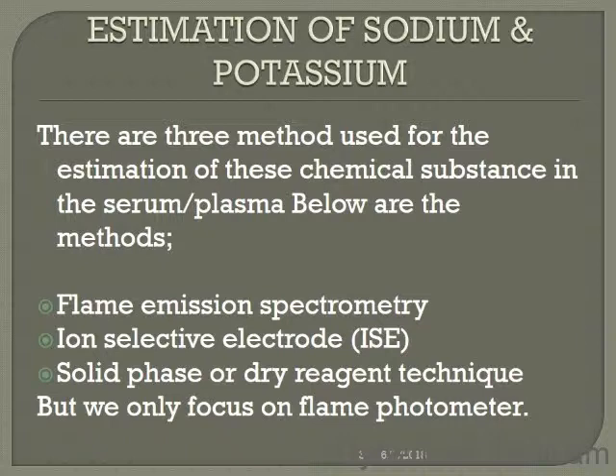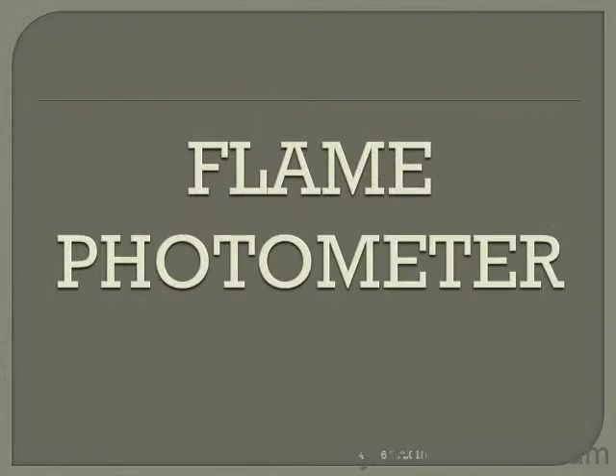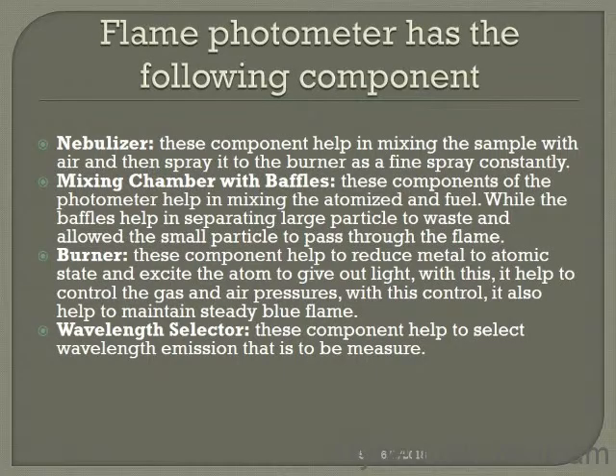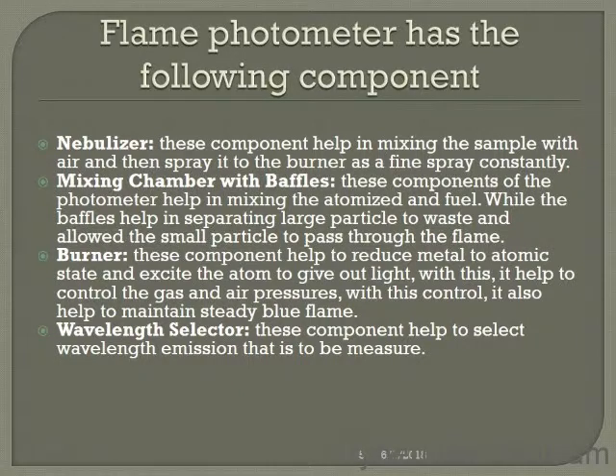We are only going to focus on flame photometry. Flame photometry has the following components. It has a nebulizer — a component that helps in mixing the sample with air and then sprays it to the burner as a fine spray constantly. It has a mixing chamber with baffles, which helps in mixing the atomized fuel while the baffles help in separating large particles to waste and allows small particles to pass through the flame. There is a burner, which helps to reduce metal to atomic state and excite the atom to give out light, controlling gas and air pressure to maintain a steady blue flame.